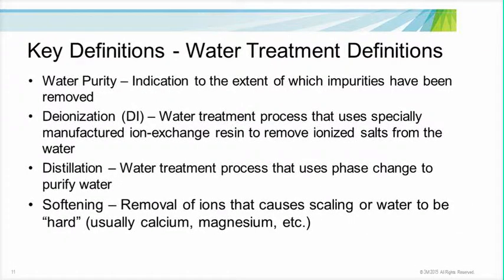The next set of definitions are specific water quality treatment definitions. And we will go into all of these in more detail later, but I wanted to get you guys a basic understanding of these definitions at this point. Water purity is an indication to the extent of which impurities have been removed based on product need. Deionization is the water treatment process that uses specifically manufactured ion exchange resin to remove ionized salts from the water. Distillation is the water treatment process that uses phase change to purify water. And softening of water is the removal of ions that cause scaling or water to be hard. And this process removes calcium and magnesium.